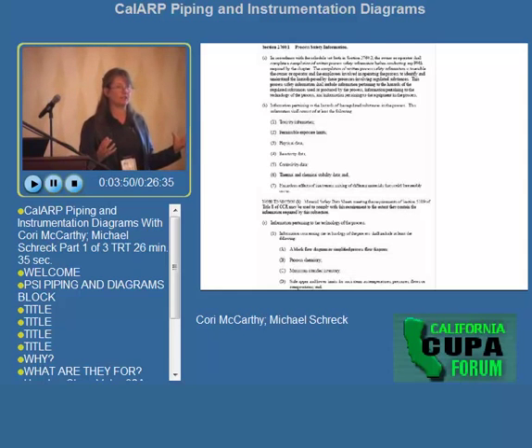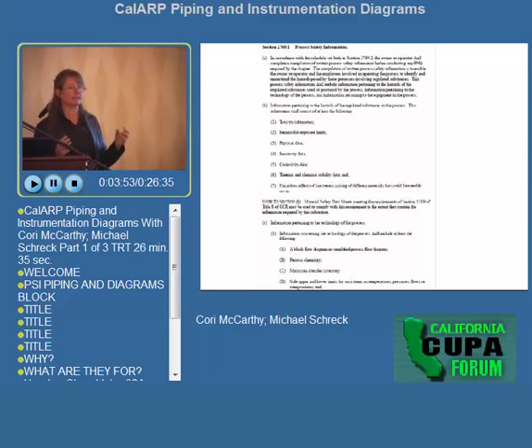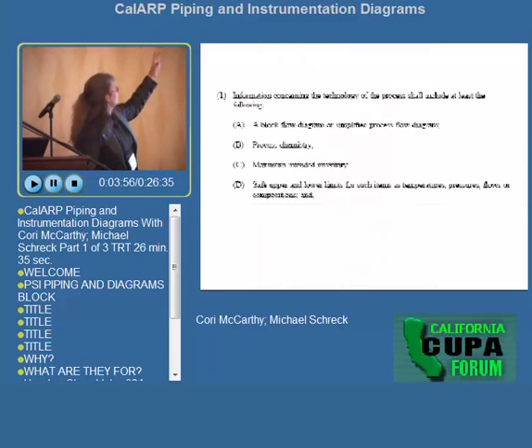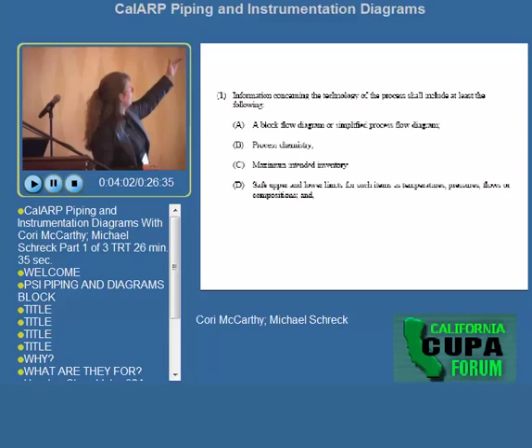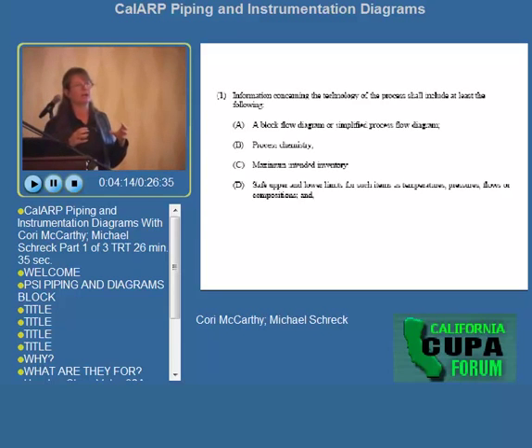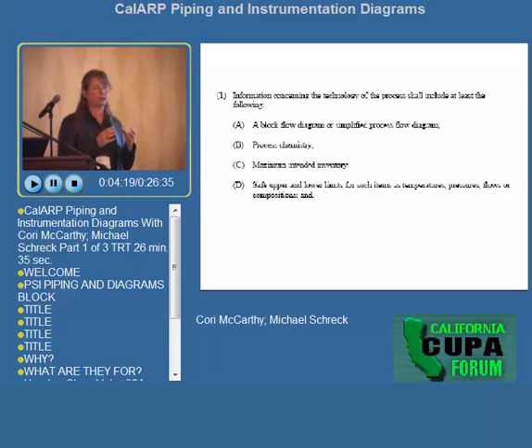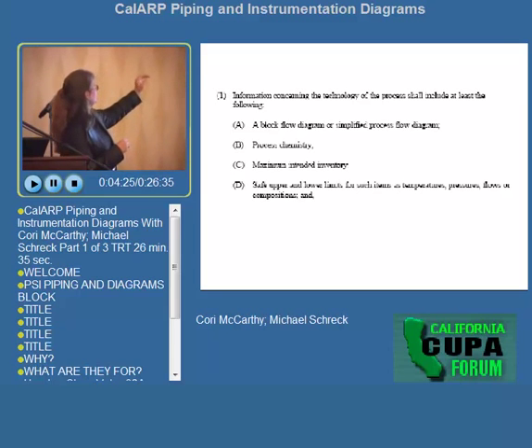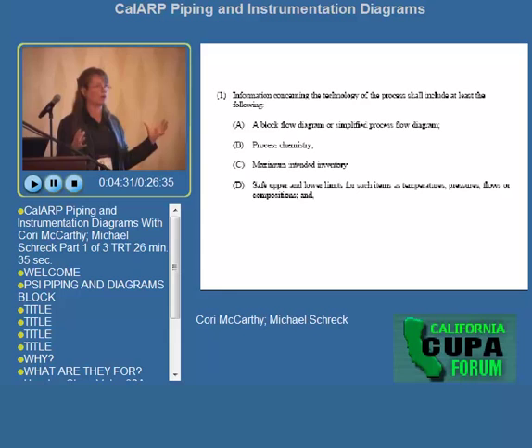If we don't know all of the information, we will not be able to effectively address all of the hazards. This section talks about a block flow diagram, a maximum intended inventory, and the safe upper and lower limits — all things that may be included on a very comprehensive piping and instrumentation diagram. You might find someone who does P&IDs so thoroughly that at every component they give you the upper and lower limits and a block flow diagram in a simpler format.